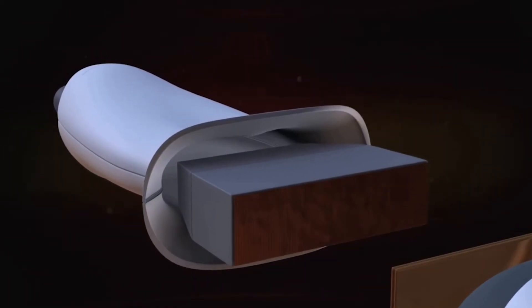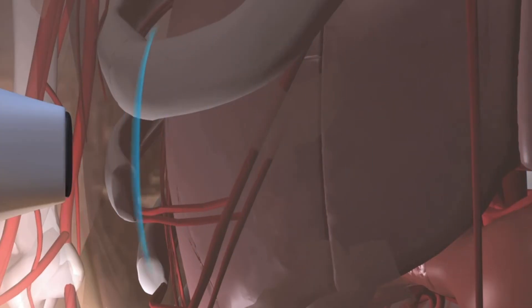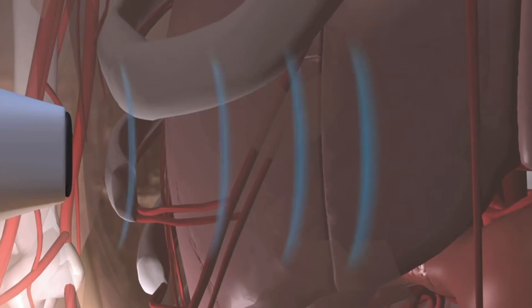It's been created for space. So how does the physics work? Ultrasound is sound waves — how is it generated by a traditional system? For the lay audience, your traditional ultrasound devices have a piezoelectric crystal that forms the transducer, the ultrasound head. They typically have around 128 elements on average for different probes. They're fairly limited and have a very fixed shape — curved probes, linear probes — tuned for different frequencies with different depth capabilities, either shallow or deep.